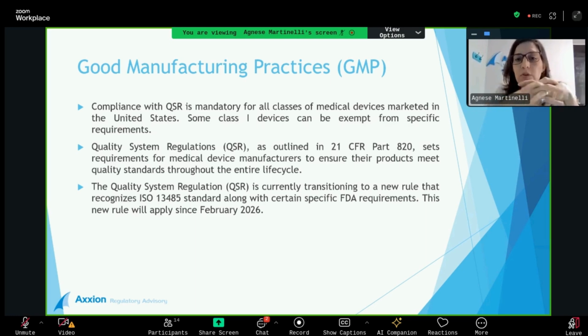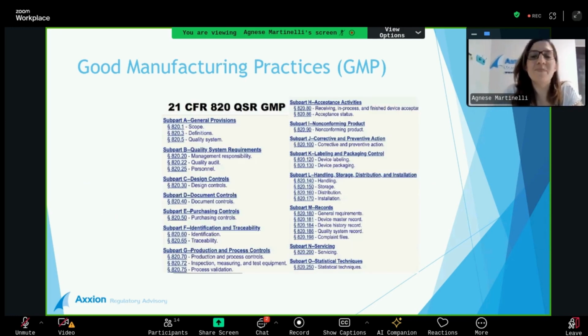The quality system regulation is currently transitioning into a new rule that recognizes the ISO 13485 standard, along with certain specific FDA requirements. This rule will only be applicable since February 2026, so we still have time to discuss it. Here we have a short screenshot of the index of the 21 CFR 820 quality system regulation, and you get to see the different parts and titles, just to get a full picture of its scope.